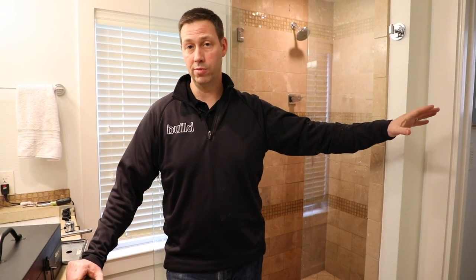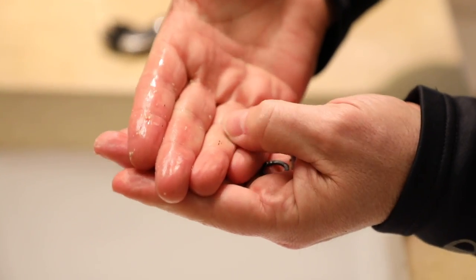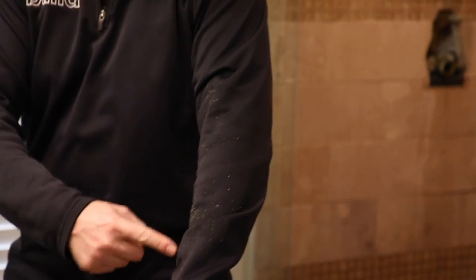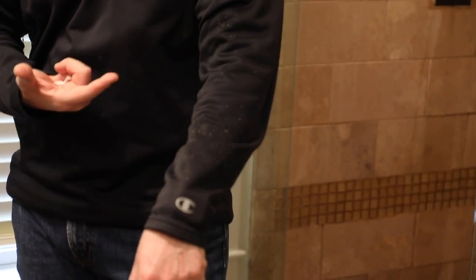The system should be mostly flushed now, but it's not a hundred percent. Very likely I'm going to have to come back in a week and take that apart if there's more scale still in the line. The unit itself should be totally good — we spent a long time descaling it — but it's possible there might be some calcium carbonate flakes remaining in the system. Funny enough, when I popped that thermostatic valve out, look at that — that's all scale that came onto my black shirt.